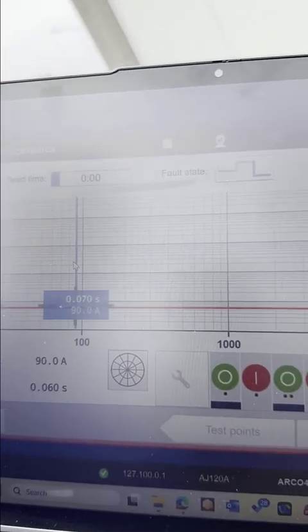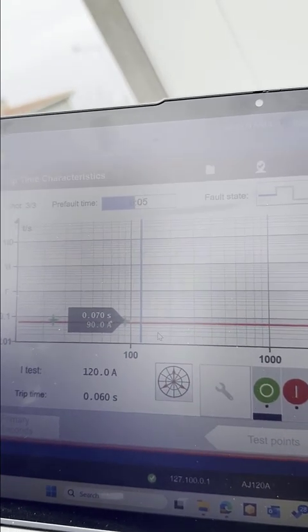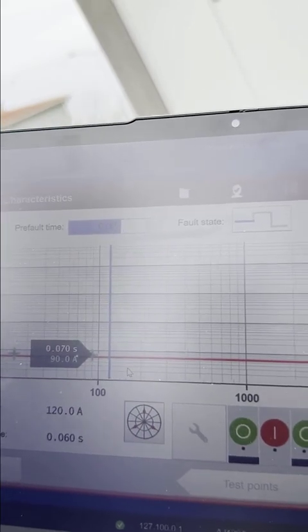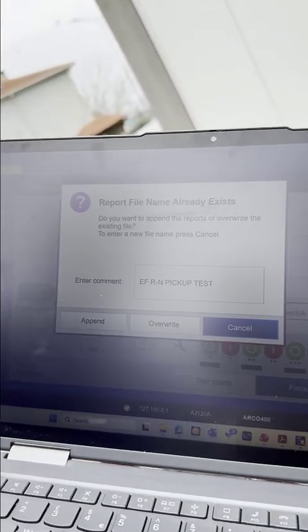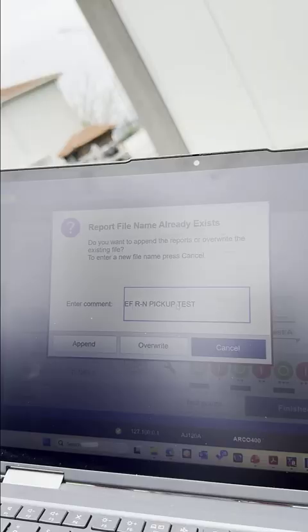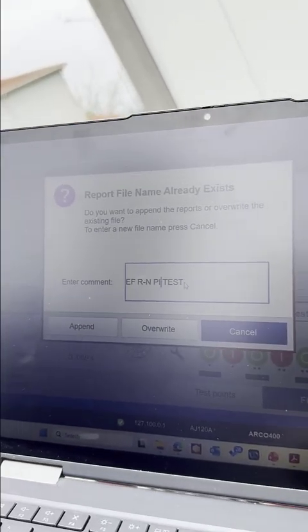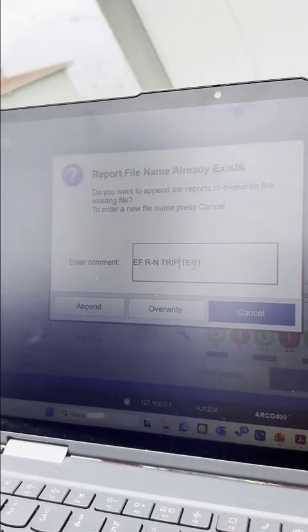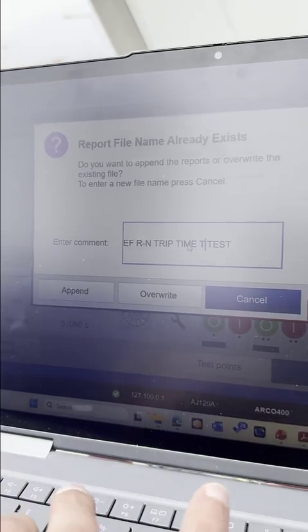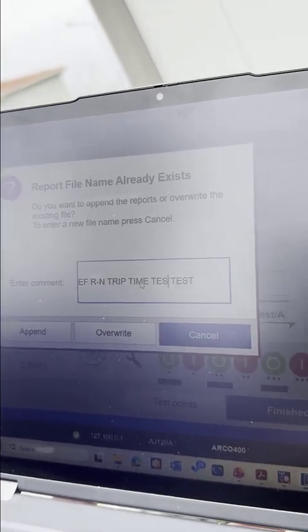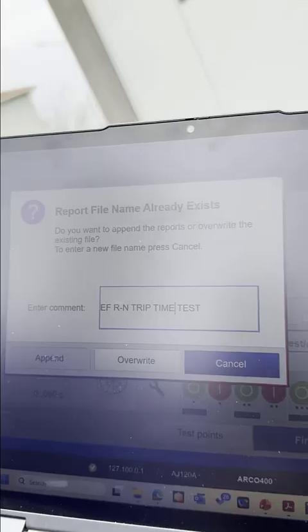Now it's in the pre-fault again, and the breaker is closed to simulate the second shot, and which is 70 millisecond. Now it's pre-fault again, and the circuit breaker is closed before the third and last shot. So now it's 68 millisecond. Now you can save this test result. You can give it a name like earth fault R to N trip time test. Then you can click append.